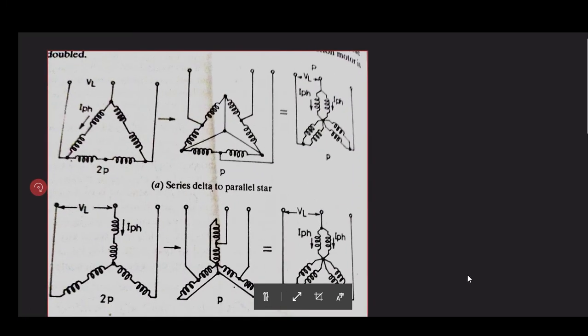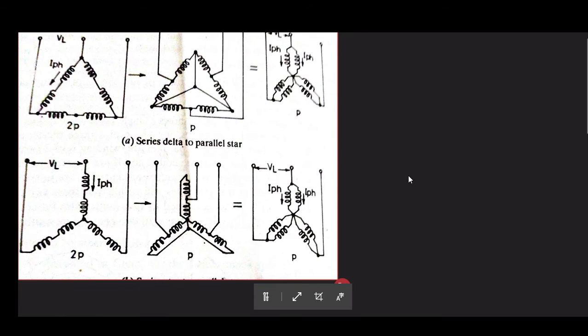Right. Now, the consequent pole changing technique is applicable for squirrel cage induction motors only. It is not suitable for slip ring, because in a slip ring machine it is not possible to design your system to have multiple poles. In case of squirrel cage, the rotor winding is free to adapt itself to any number of poles. So we can do some manipulation with our winding.